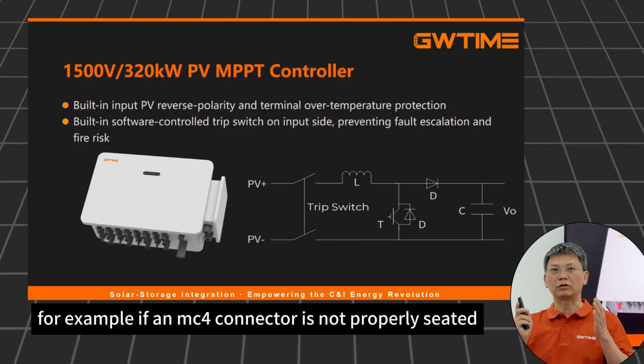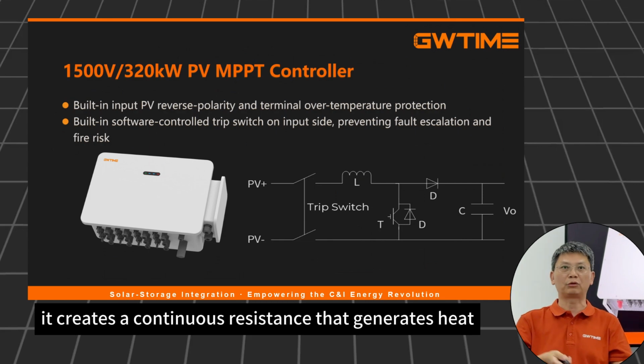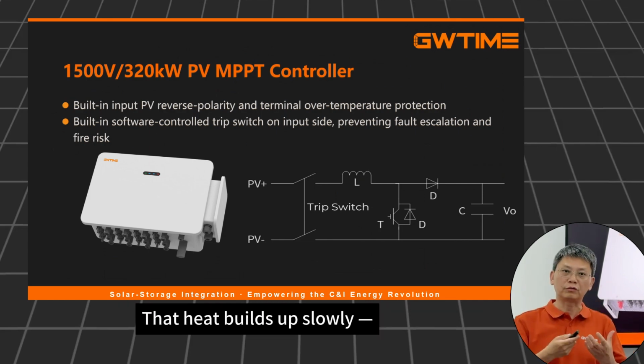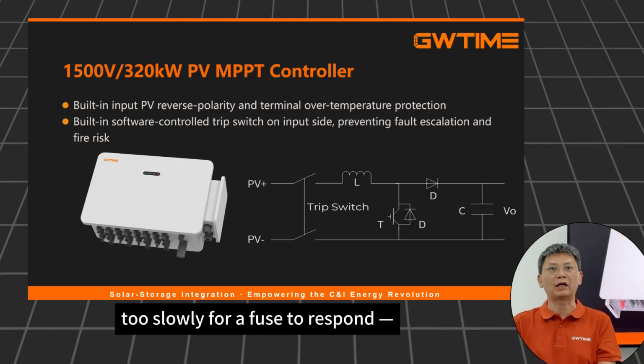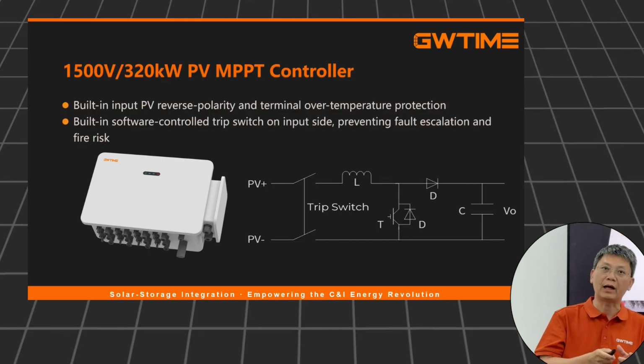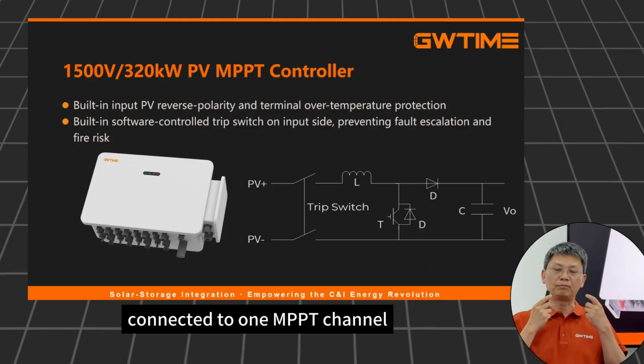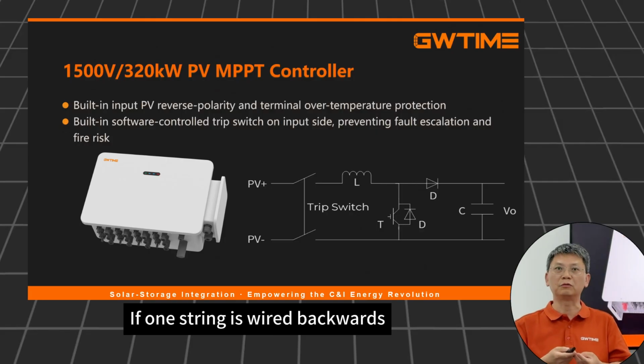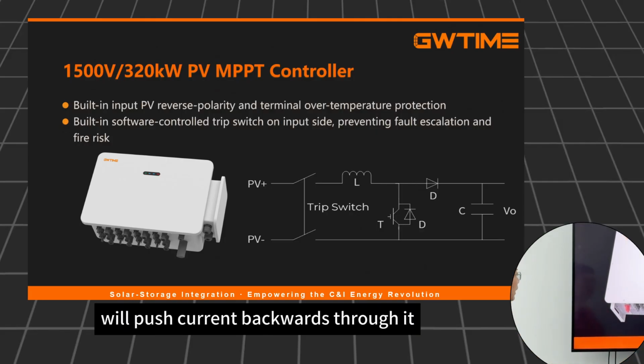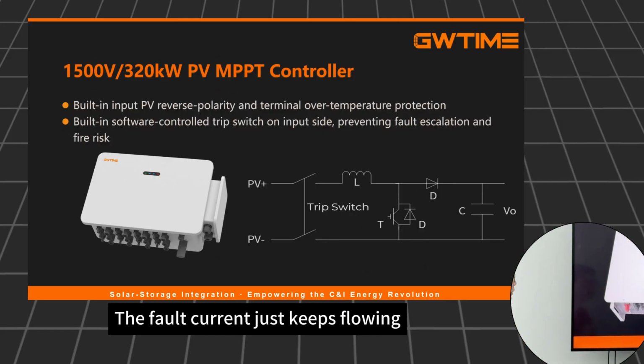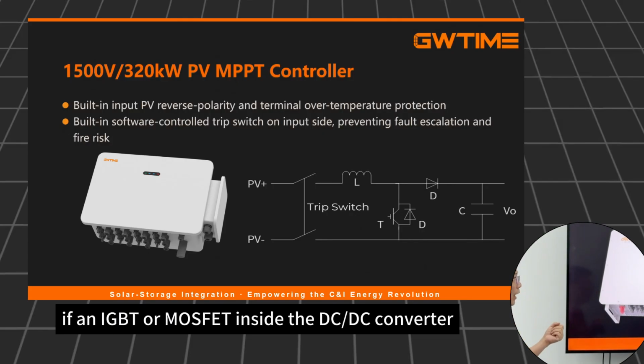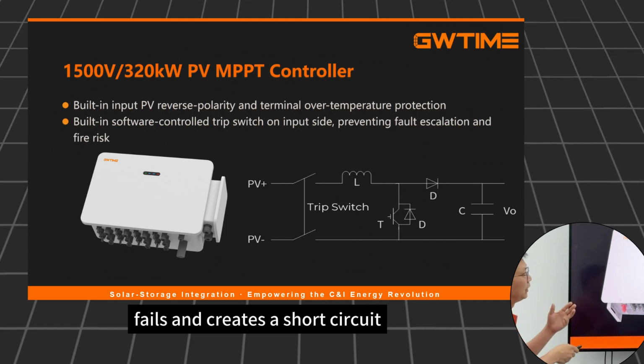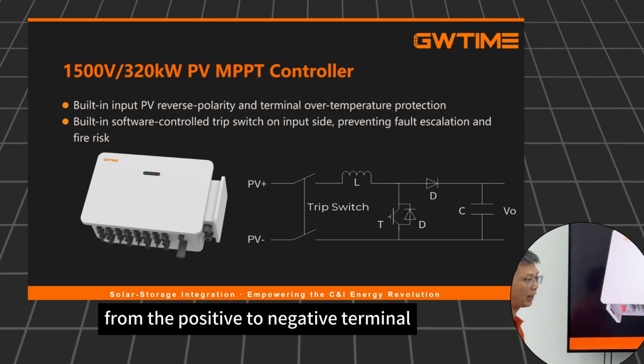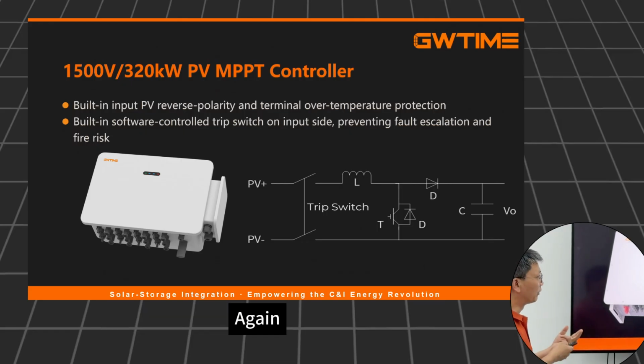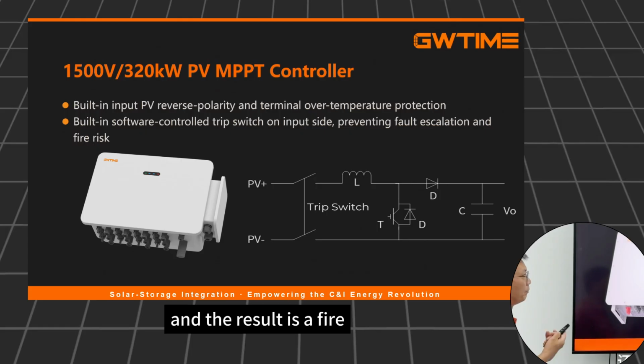For example, if an MC4 connector is not properly seated, it creates a continuous resistance that generates heat. That heat builds up slowly, too slowly for a fuse to respond, and can eventually start a fire. Consider 3 strings connected to one MPPT channel. If one string is wired backwards, the other 2 strings will push current backwards through it. No breaker trips, no fuse blows, the fault current just keeps flowing. Similarly, if an IGBT or MOSFET inside the DC/DC converter fails and creates a short circuit, current flows continuously from the positive to negative terminal of the array through the failed device. Again, nothing interrupts it, and the result is a fire.